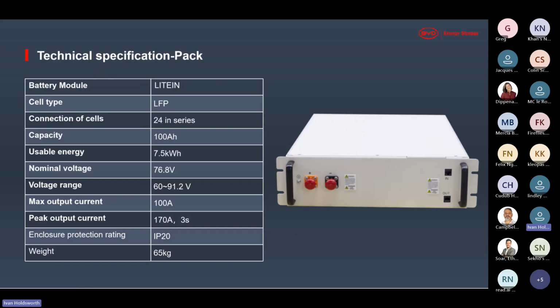And here we can see the battery module. Number of cells in series is 24, and it's 100 amp hour. And your voltage range for that module is between 60 and 90 volts, approximately. And it's also 100 amp output.